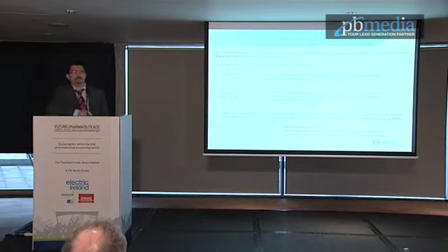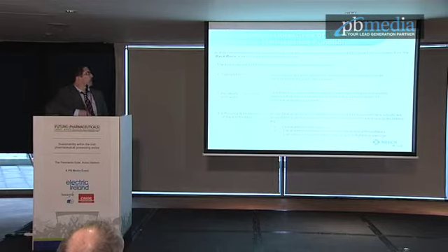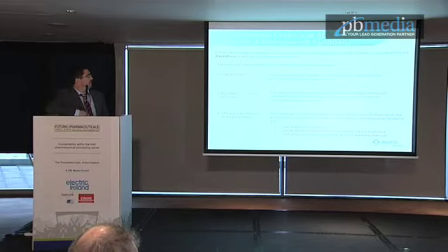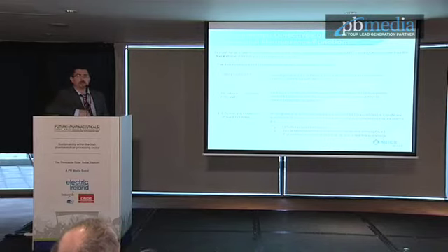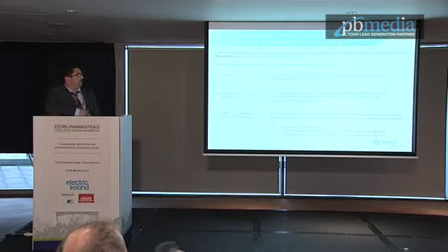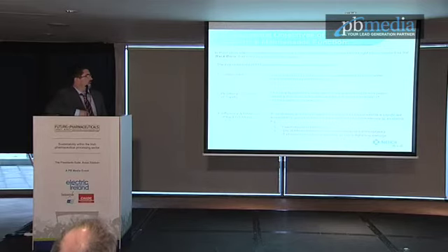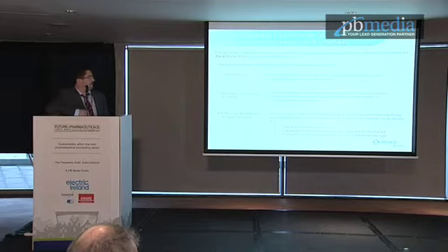So that then caused us to focus our attention on the electrical asset and how we should actually be maintaining it. In most large-scale sites, the electrical system can be considered as the backbone of all activities on site. So it should fall under three main headings. We look at the safety of the asset to make sure it represents no hazard to personnel or users interacting with the system. We need to look at reliability and continuity of supply to make sure it doesn't inflict any serious losses to production. We also need to look at efficiency and protection of the asset to make sure that we've no inadvertent abuses or incidents.